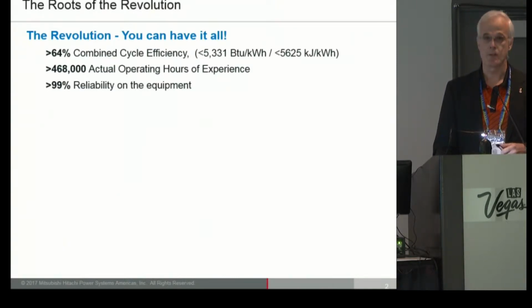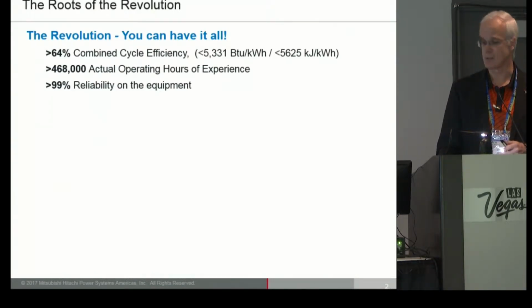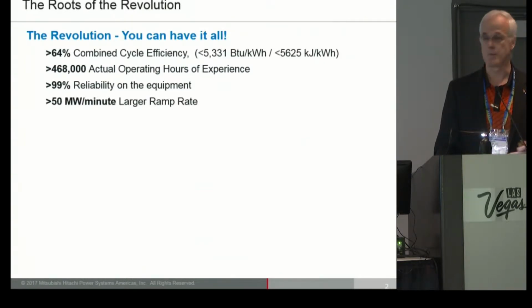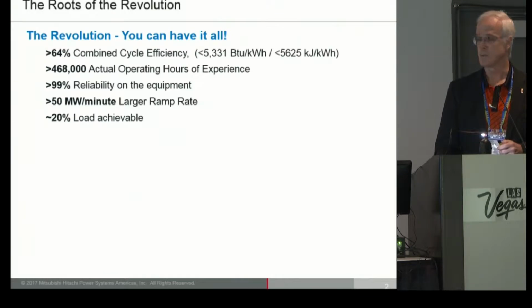Over 99% reliability - our J fleet, like our G fleet, has over 99% reliability in operation to date. We can ramp at roughly 50 megawatts a minute, a significant difference to keep up with the larger dispatch as the grid moves these days for quicker response. We can also get down to 20% load with our gas turbines now, which helps significantly with renewable backing and balancing out grids as renewables come up very quick.